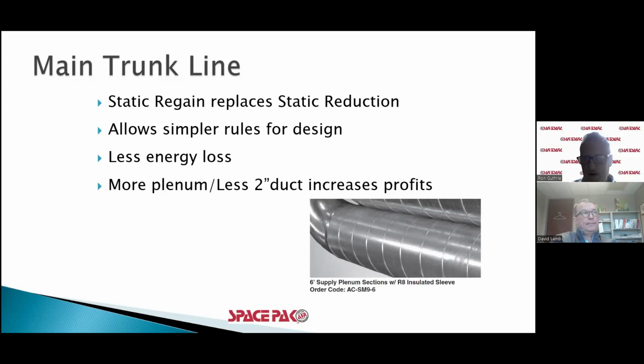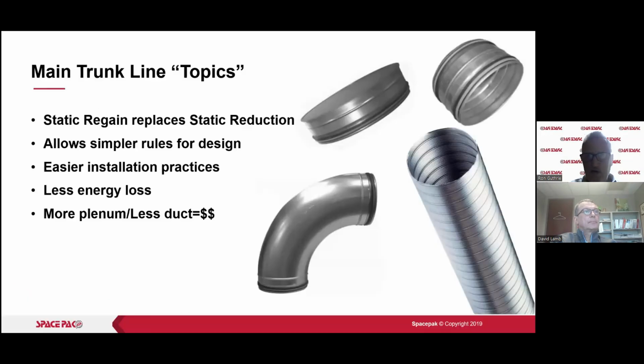That's where the real pressure drop is, in the 2-inch duct, and those are critical to keep at 15 feet or lower if we can, or to compensate for longer runs. So, always put some more plenum on to get a little further down if it's going to keep your 2-inch duct runs shorter.